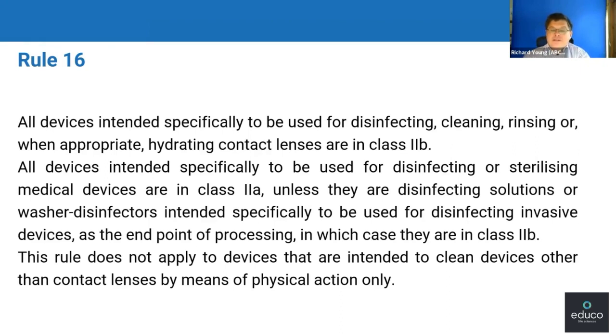It also talks about devices which are going to be used for disinfecting or sterilizing medical devices. So this could be something like a benchtop sterilizer in a dentist surgery. Equally it could apply to washing and sterilizing equipment that's used in hospitals. Those are all medical devices and fall under the medical devices regulations as class 2A and need to be CE marked in accordance with those requirements.